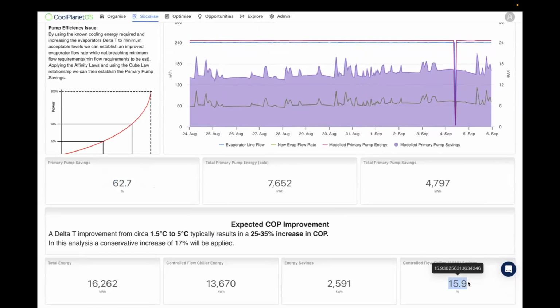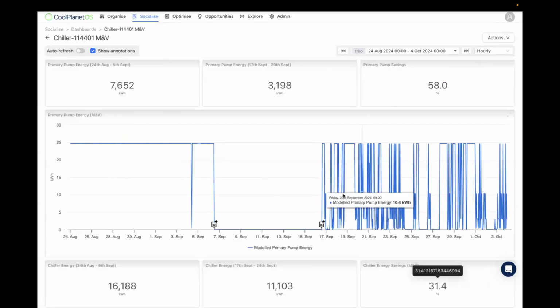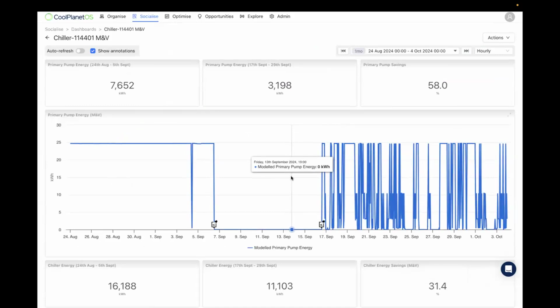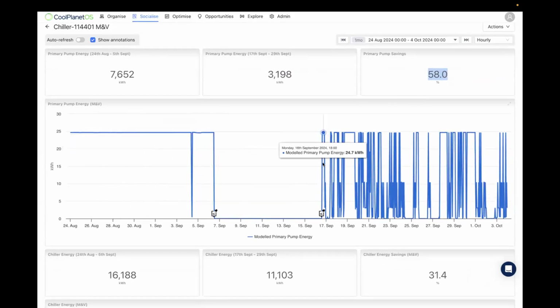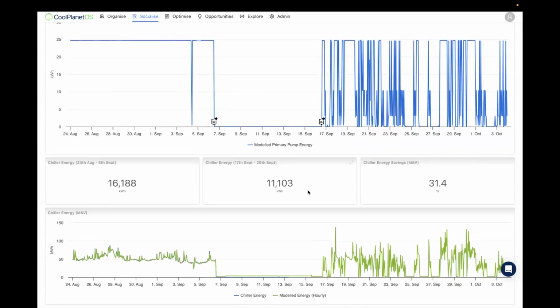16%. So the next step here was to implement those control changes, send a control change document to the client, they would implement it, and then we would carry out a measurement and verification analysis as we would on every kind of solution. So in that theorized analysis, the pump savings was 62. We achieved 58. You can see the before and after here of the pump energy. And similarly with the chiller, the before and after, and we achieved 31% savings. So across all four chillers, this equated to 133,000 in financial savings. So huge impact on cost and energy and carbon around your scope two.